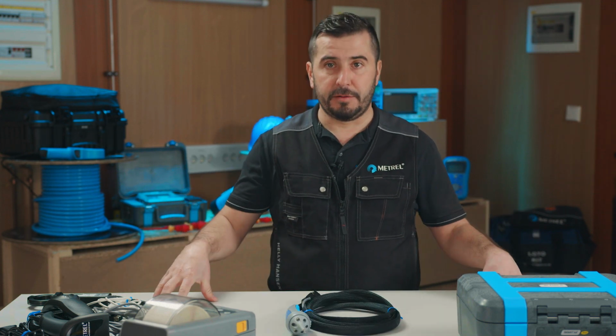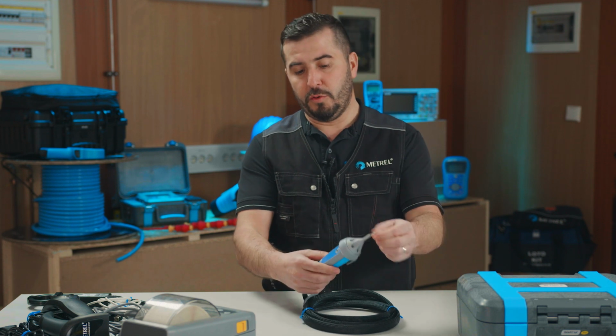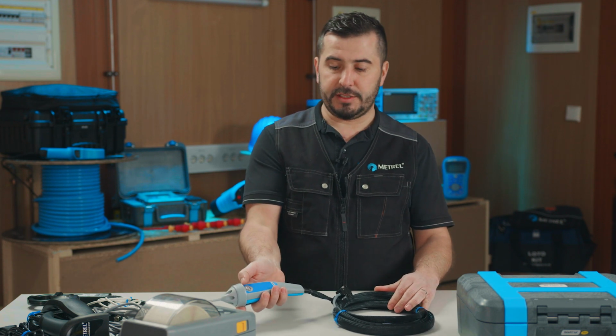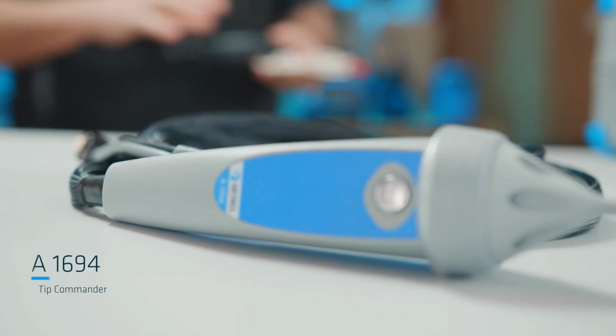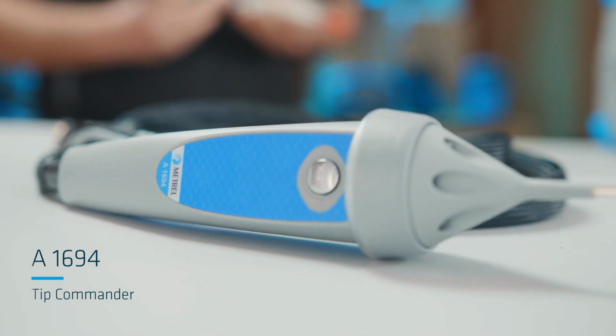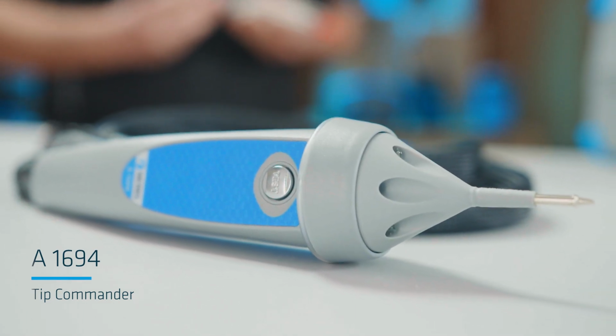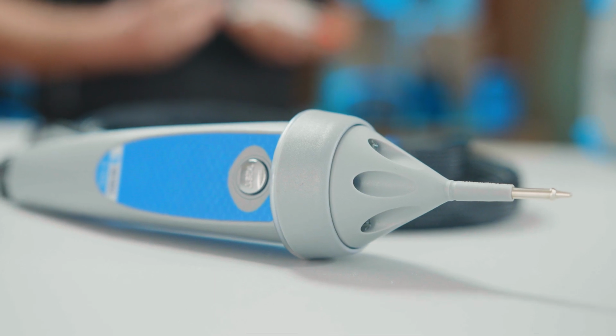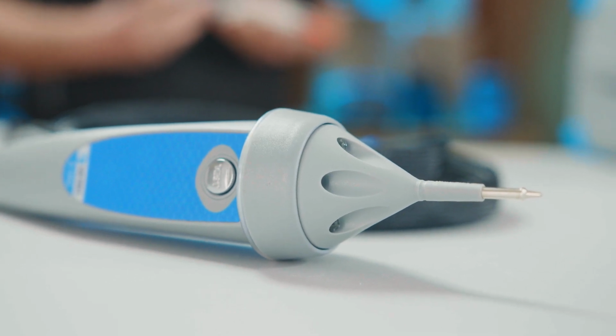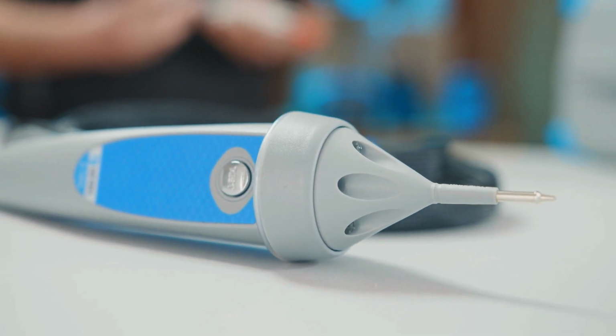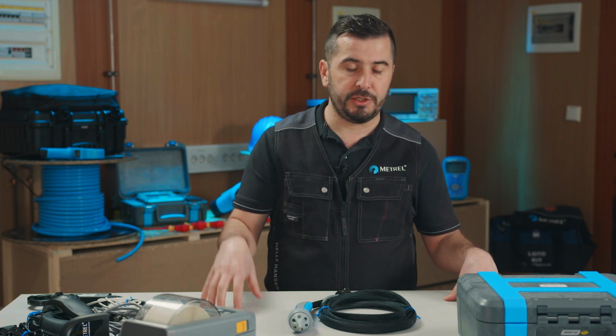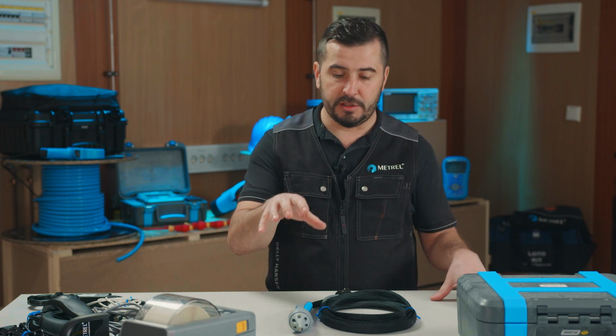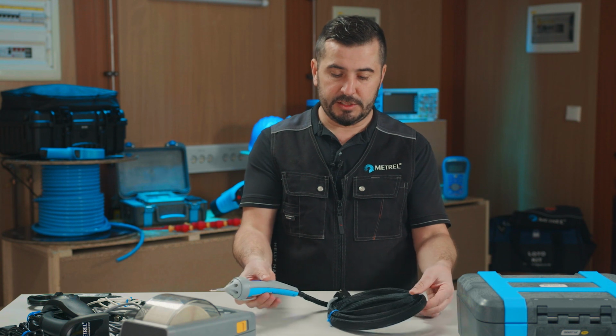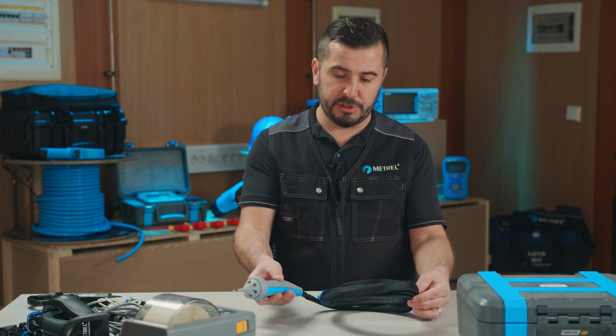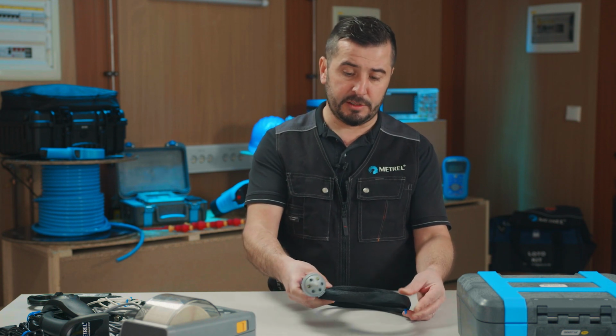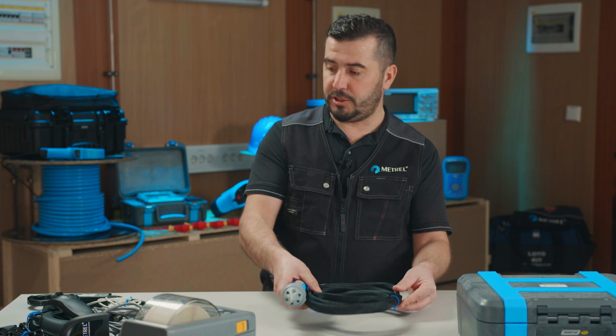Then we have this probe or tip commander, which has an integrated test button here. So this one is specially designed for measurements where the probe is needed, either for earth continuity measurement or measurements of insulation resistance with probe, touch leakage, or other measurements where the probe is needed. So this is again one very good piece of equipment which is available as an optional accessory.